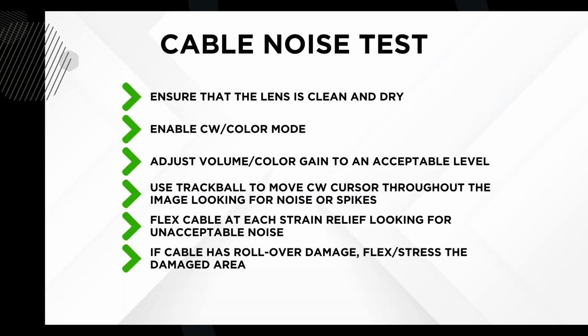Good. So I would do that in both. Same two tests for color and pulse wave or continuous wave. And then on some transducers, I would take this cursor up here. We call this a sample volume, and I would scroll through the whole image of the transducer as well to see if there's any other issues. And sometimes when you scroll through, you can start to see some noise and some issues.